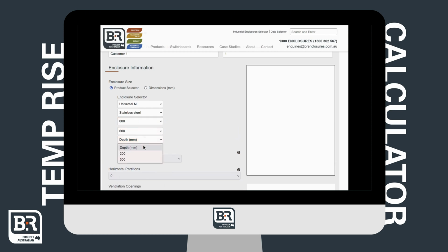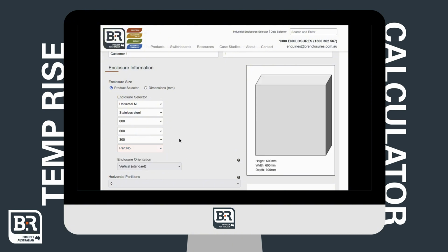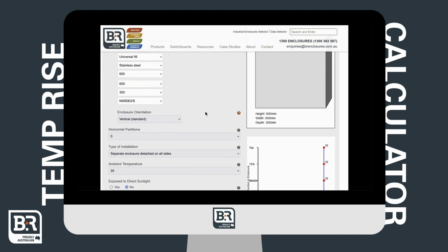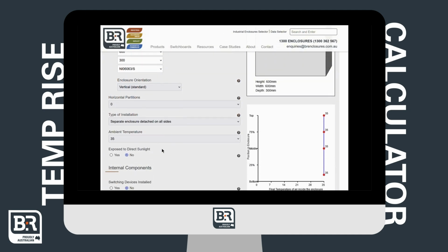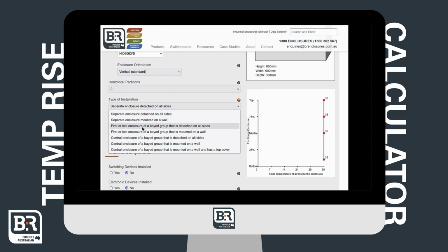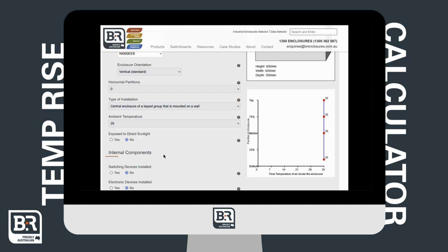A standard NI series stainless steel enclosure is selected. 600 high, 600 wide, and 300 deep. There's only one part number for that size. The enclosure will be wall-mounted vertically with no partitions. Ambient temperature is set to 35 degrees, and it's not exposed to the sun. This results in an initial temperature rise of around 4 degrees.